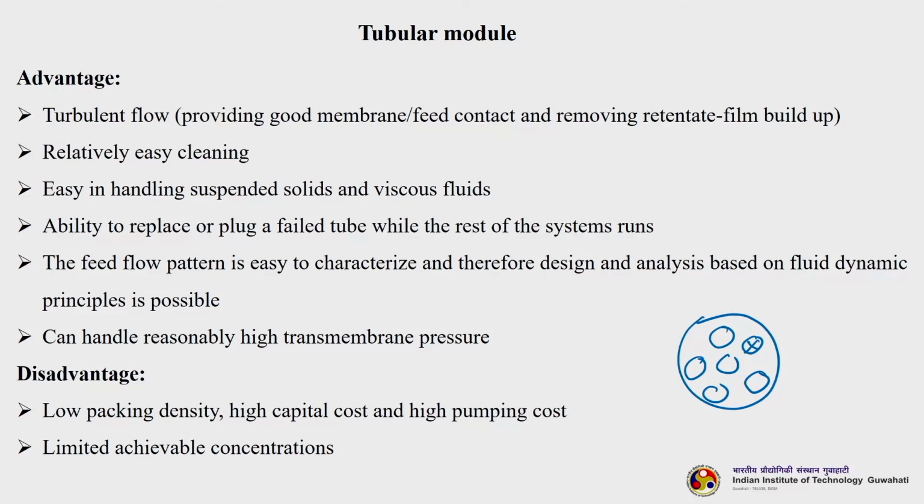Usually I can open the membrane module and replace this particular tube with a new one, or I can plug it. I can seal it from both ends, so that particular membrane module is not taking part in separation. That is why this type of tubular system is really advantageous when we are using it in industry or large scale applications.